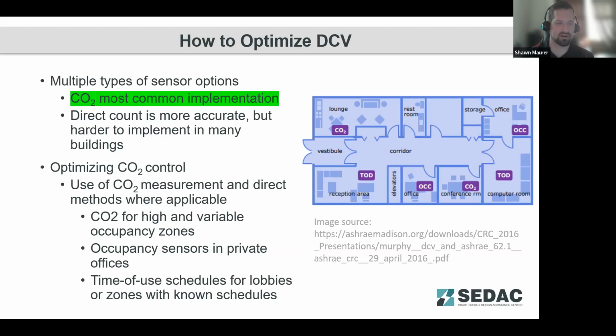CO2 for high and variable occupancy zones. Occupancy sensors can be used in private offices where you know it's just that one occupant, and so your ventilation can be tied directly to that occupant's presence. And time of use schedules are good for lobbies or zones with known schedules, relatively consistent occupancy rates. And this has a couple of benefits. One, you're going to get better performance out of your ventilation system. And two, you're going to mitigate the cost of having a bunch of sensors that aren't really as effective as they could be if you're trying to put CO2 sensors in every space. Or as we sometimes see, putting those CO2 sensors in a return duct or something like that, where it's averaging multiple spaces. And now those individual spaces don't necessarily get the ventilation they need when they need it.